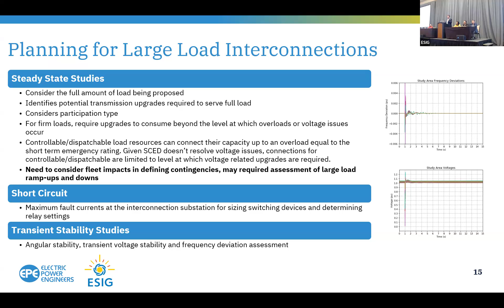Transient stability, for the most part, angular stability, transient voltage stability, and frequency deviations. We're really looking here at the loss of the load, or in some cases, the reconnection of the load without actually clearing it with the ISO or the utility ahead of time. So these are situations where you want to look at if the load was to fully reconnect or if the load was to disconnect, what could be the angular stability issues, what could be the transient voltage issues that you see, as well as any frequency changes. So these are the baselines that we're all really used to.